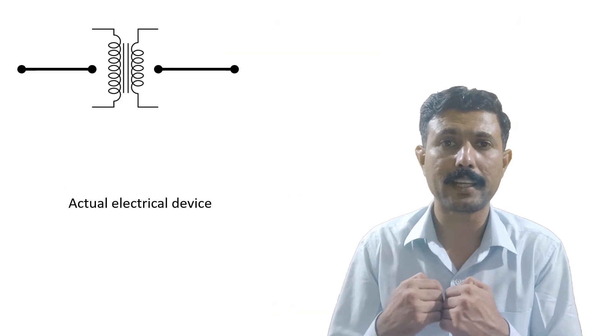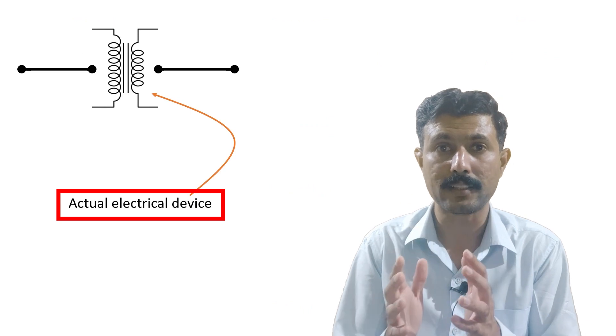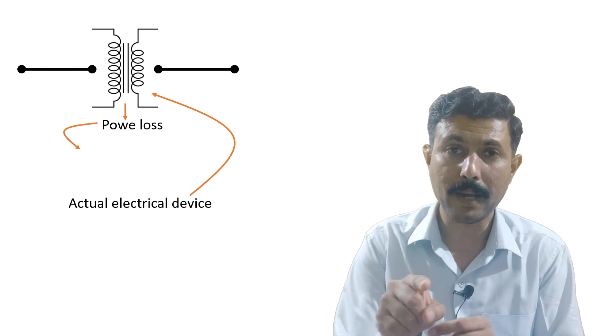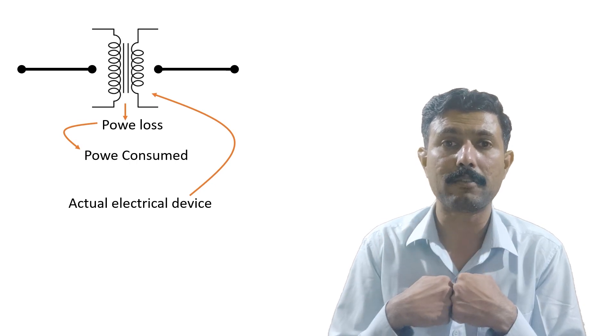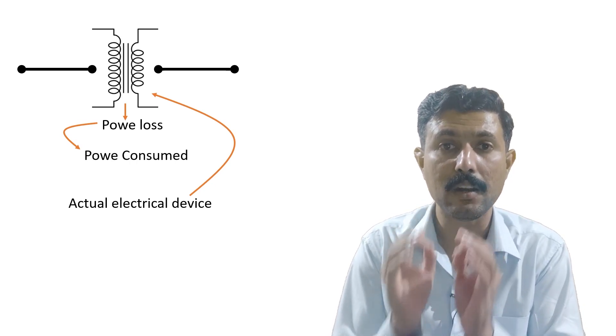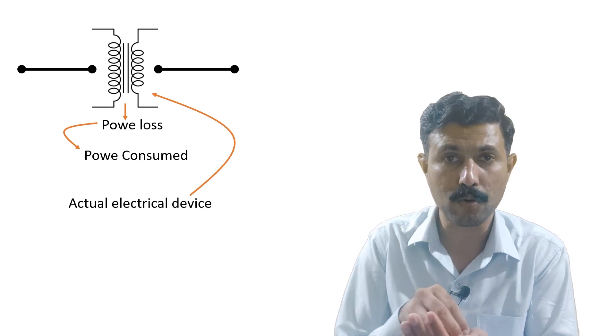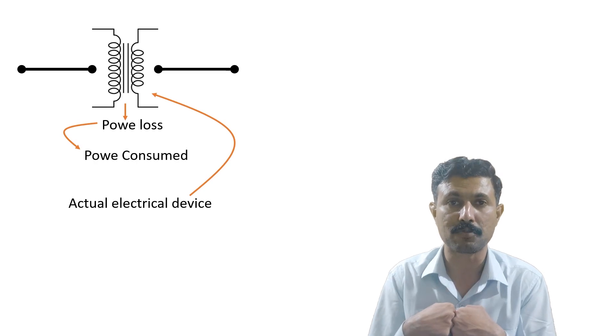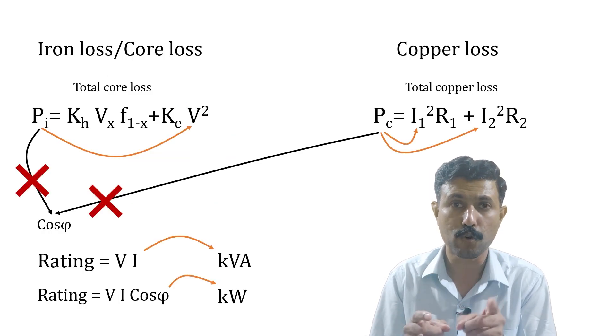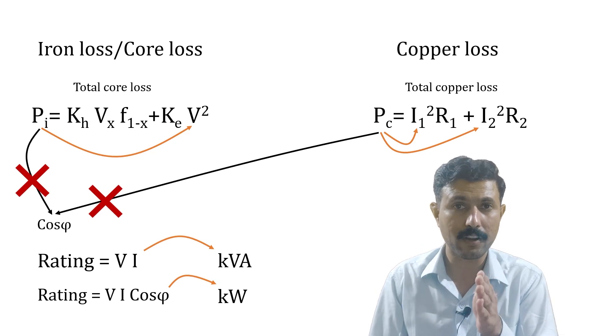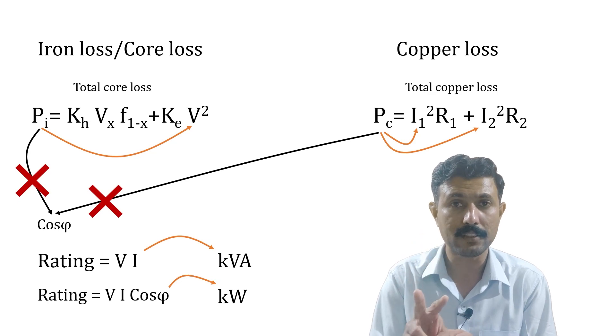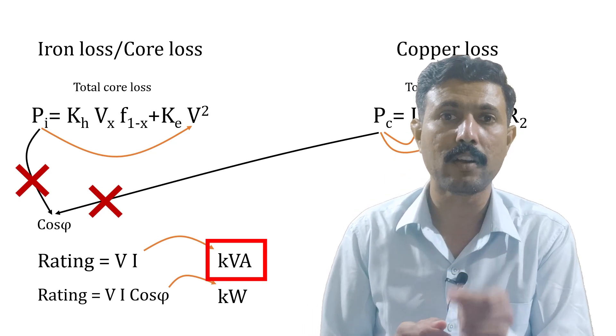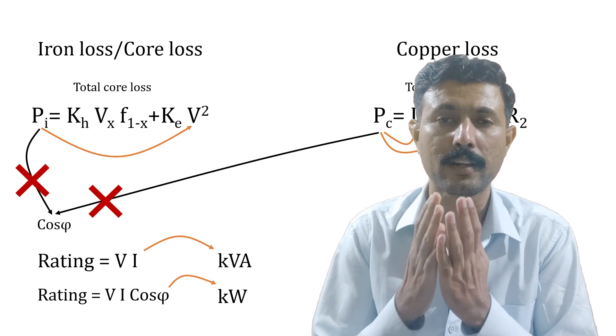Though the transformer is not a load and does not consume power, it is an actual electrical device, and any real electrical device has power losses. Those losses are considered as the power consumed by the transformer when treating it as a load. There are two types of losses: copper loss, which depends purely on current, and iron loss, which depends on voltage. Neither depends on power factor — and this is why the rating of a transformer is VA, KVA, or MVA, not watt, kilowatt, or megawatt.